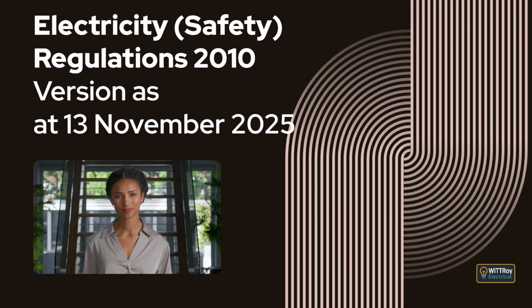This regulation explains that every certificate of compliance must record whether high-risk work on a low or extra-low voltage installation was done in accordance with Part 1 or Part 2 of AS/NZS 3000, whether the work complied with a certified design, and whether any standards other than, or in addition to, AS/NZS 3000 were complied with. It also explains that the certificate must record whether the work relied on manufacturer's instructions, the type of supply system the installation or part installation is safe to connect to, and which parts of the installation are safe to connect to a power supply. It then explains that further identification details about the installation, the work, and the persons involved must also be included. Reg 68 Who may issue Certificate of Compliance.